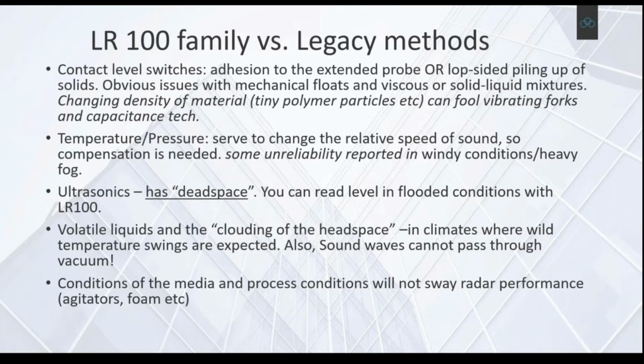With ultrasonics, while they're championed because they've always had dedicated controllers and are pretty reliable, there are certain cases - like fuel oils or acids generating blankets of vapor - where it would change the velocity of sound in that headspace. This is where radar is unaffected. Radar just travels through - it can travel through a vacuum, even through space. So it's not dependent on the temperature or pressure conditions of that empty space in your vessel.